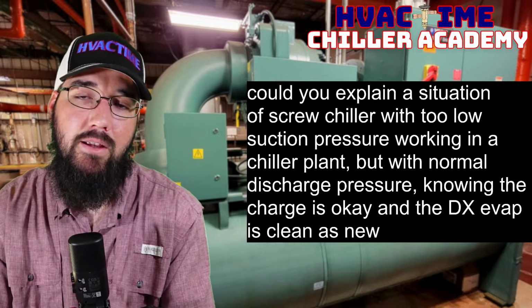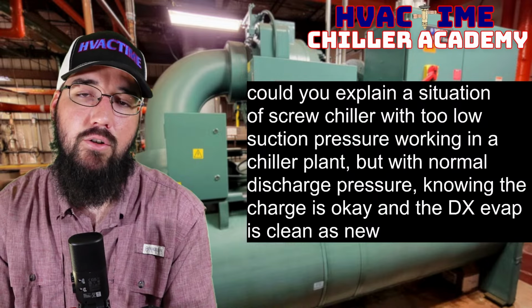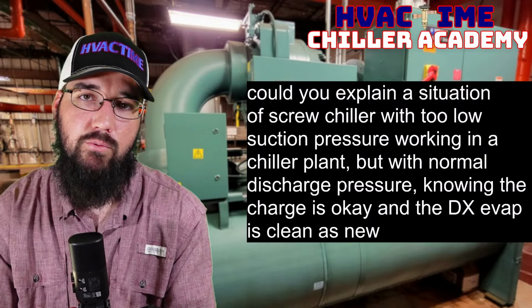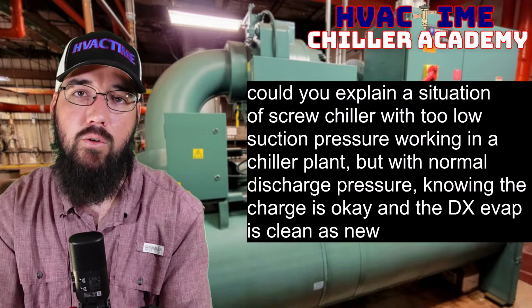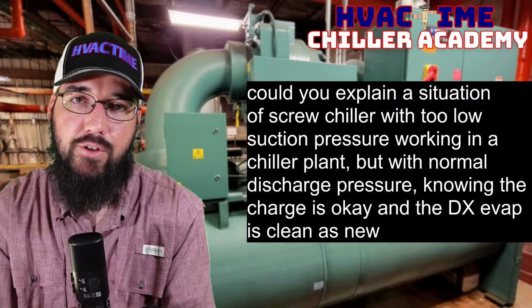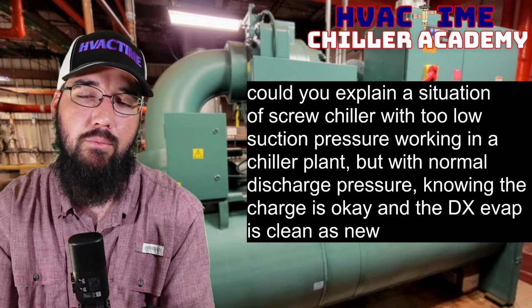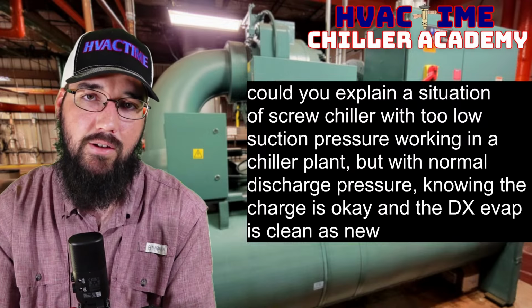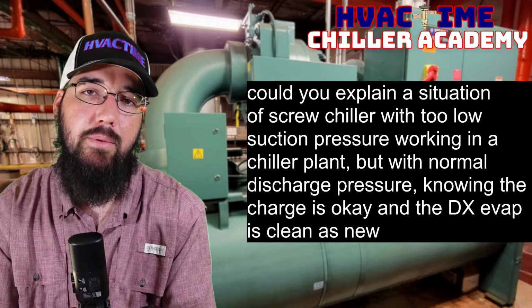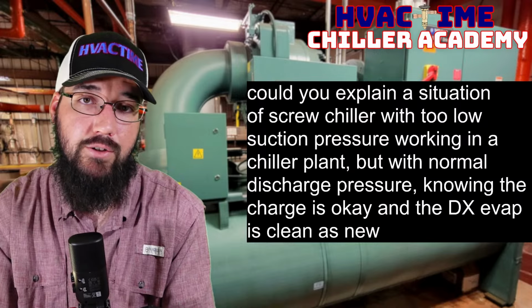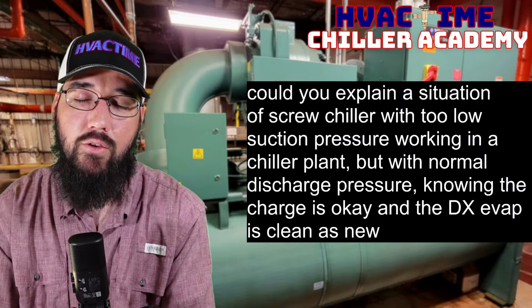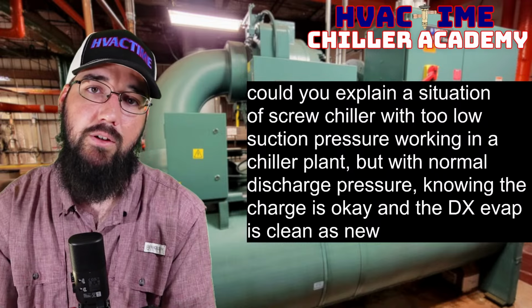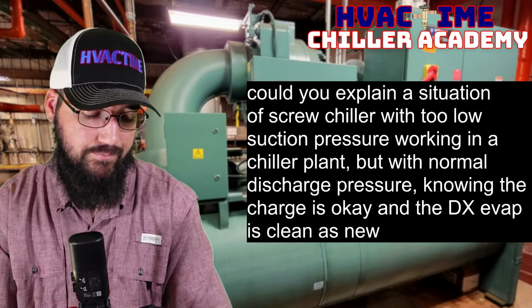So what that means is that your discharge pressure is still going to look relatively normal, because it still just has to reject however many BTUs the evaporator takes in, and however many BTUs happen in the heat of compression inside the compressor. Those two things are what the condenser has to get rid of.